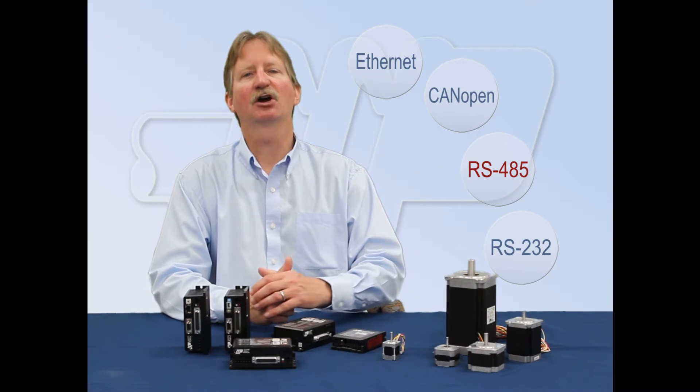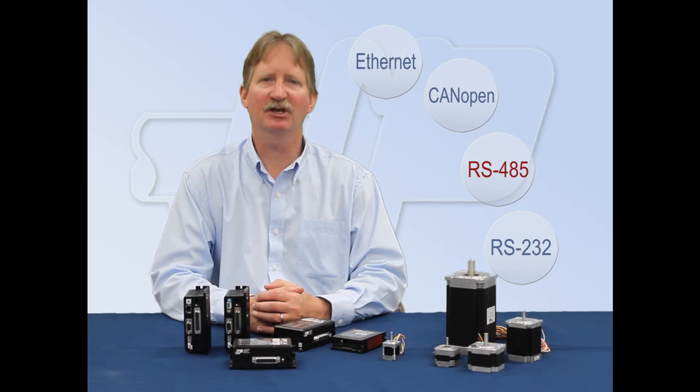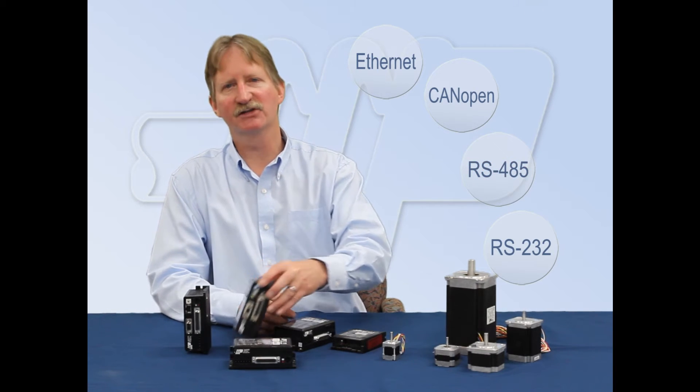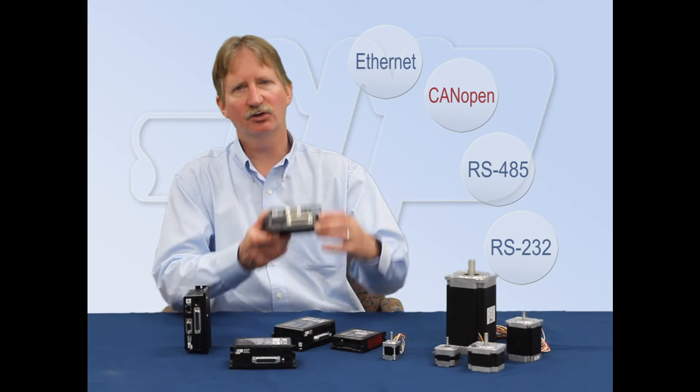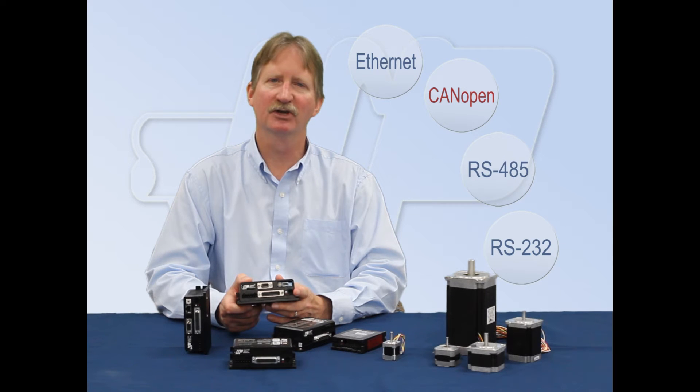Communication speeds are up to 115 kbits per second. The STQ and STSI models can also be ordered with an encoder interface for position monitoring, position maintenance, and stall prevention. The ST5C and ST10C include CANopen, allowing up to 127 axes to be controlled on a single network at speeds up to 1 megabit.